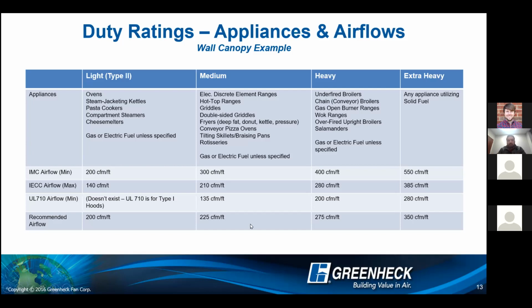The first thing that I'm going to call out here is that IMC no longer classifies UL 710 listed hoods, which all Greenheck Type 1 hoods are, based on temperature. They used to do it on temperature. Now they just have light, which is Type 2, and then medium, heavy, or extra heavy. Extra heavy being for a solid fuel application. And just know that if you have an extra heavy hood classification, that needs to be on its own grease duct system. So again, solid fuel needs to be on its own grease duct system with its own hood. There can't be other appliances, gas or electric, underneath that hood.